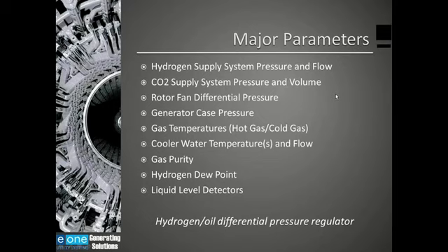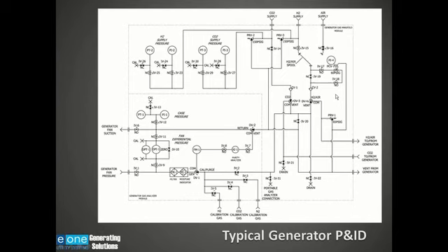Another device that is of importance when it comes to the hydrogen is the differential pressure regulator that maintains a set differential pressure between the seal oil and the hydrogen. This is a typical generator P&ID, the hydrogen system for a generator, and we're going to spend some time on this slide. Up here you can see your supply gases, and again we're using CO2 as our purge gas, hydrogen supply, air supply, and then this manifold is used to feed gas in and out of the generator. These are the connections that go to and from the generator.